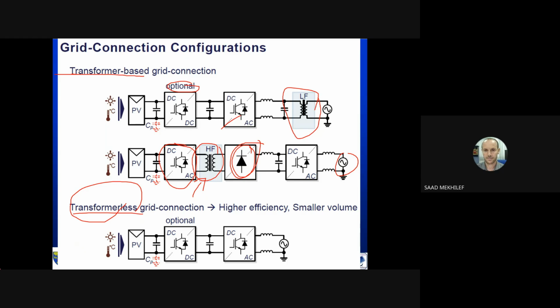So controlling this is very important, to control the leakage current and the common mode voltage. So these are quite important factors in order for us to design. So these are the two grid connection options, especially for grid connection applications. It's either transformer based or transformerless. Within transformer, we have two configurations: low frequency and high frequency transformers. Both of them are good. They provide good isolation. However, the high frequency one has another conversion stage which gives maybe lower efficiency. The transformerless is another option which is small and efficient. However, in terms of safety, it's a concern, which is the problem of leakage current. So those are the configurations that we see.